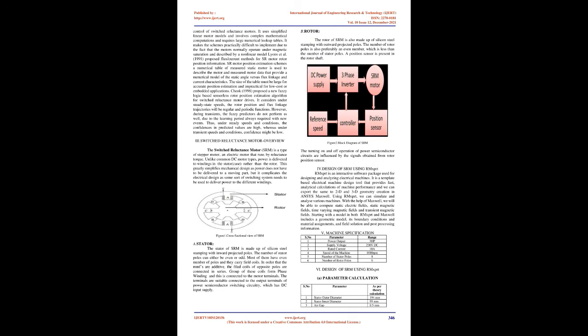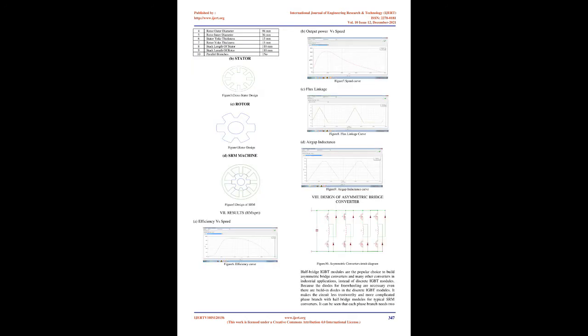Cheok (1998) proposed a new fuzzy logic-based sensorless rotor position estimation algorithm for switched-reluctance motor drives. It considers that under steady-state speeds, the rotor position and flux linkage trajectories will be regular and periodic functions. However, during transients, the fuzzy predictors do not perform as well due to the learning period always required with new events. Thus, under steady speeds and conditions, the confidences in predicted values are high, whereas under transient speeds and conditions, confidence might be low.